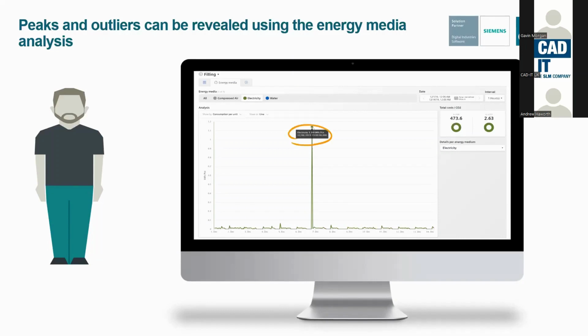However, looking at the electricity consumption per piece produced at the filling line, he spots an abnormal spike. So the filling line is now the area that could be the anomaly that's causing this increase in energy consumption. And this spike occurred at a particular time, in this case on the 6th of December at around 7 p.m.